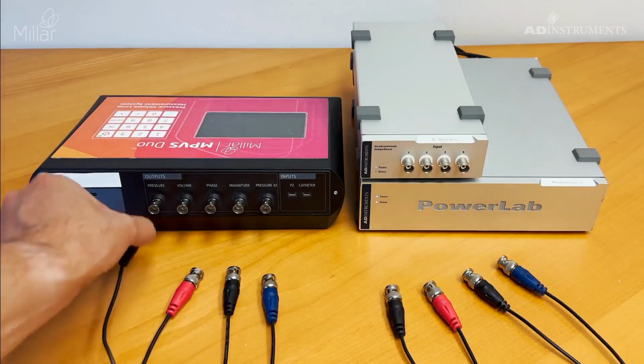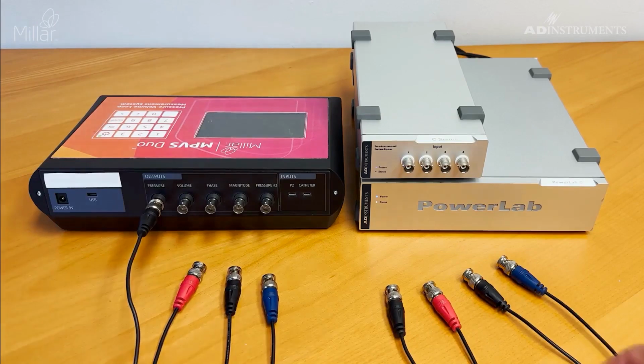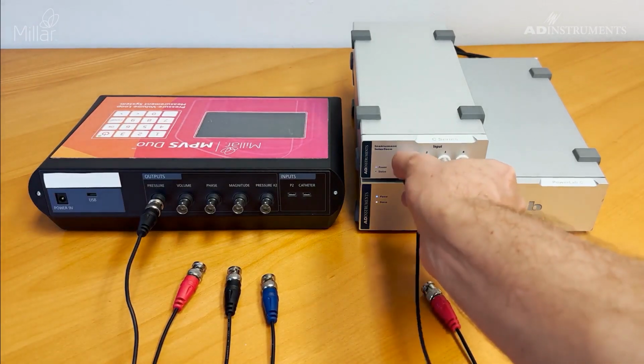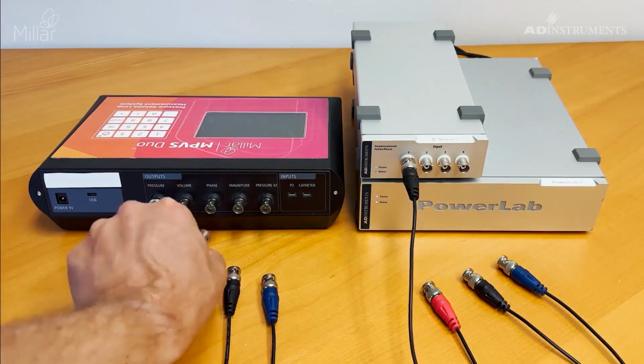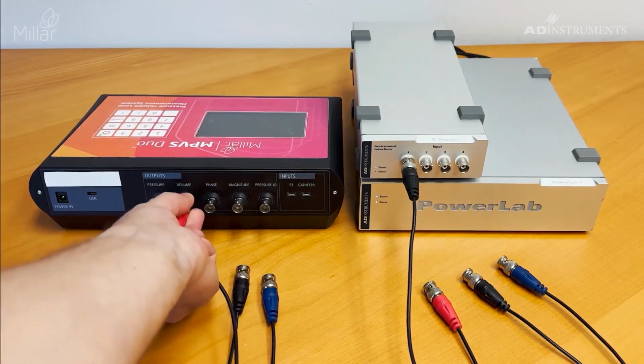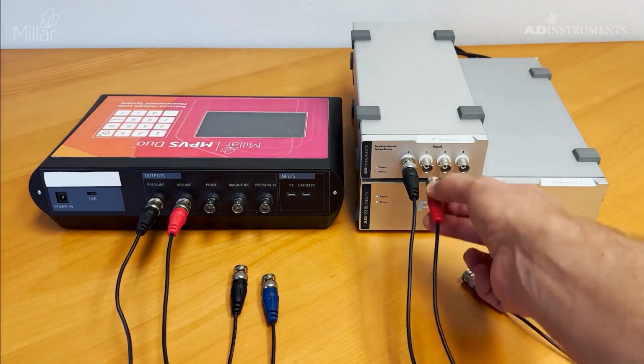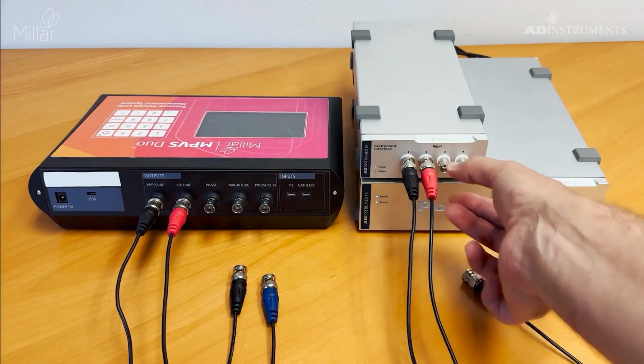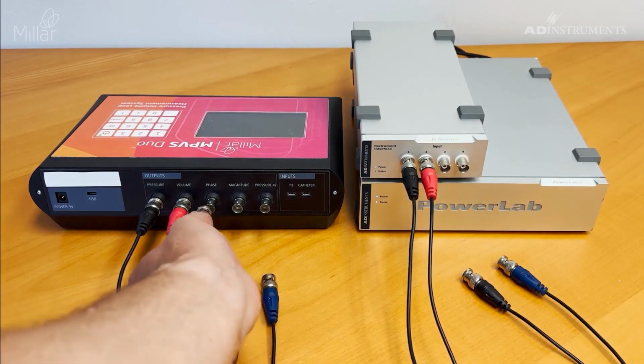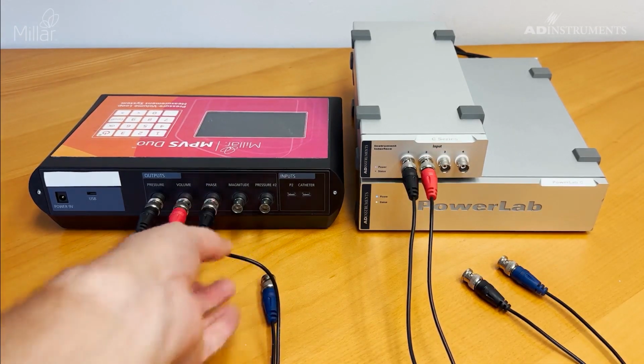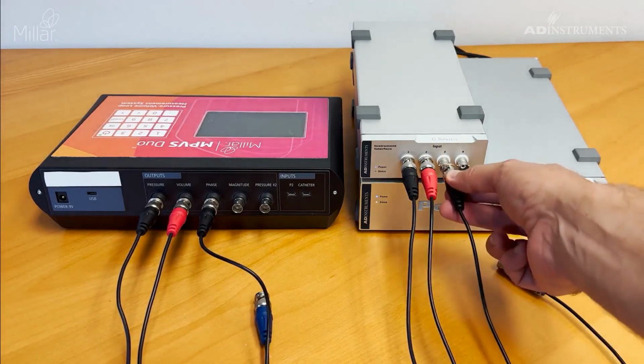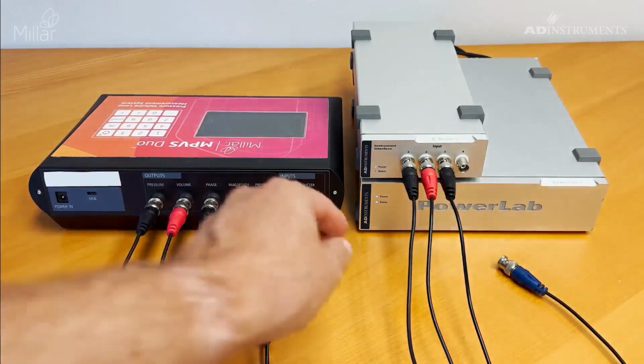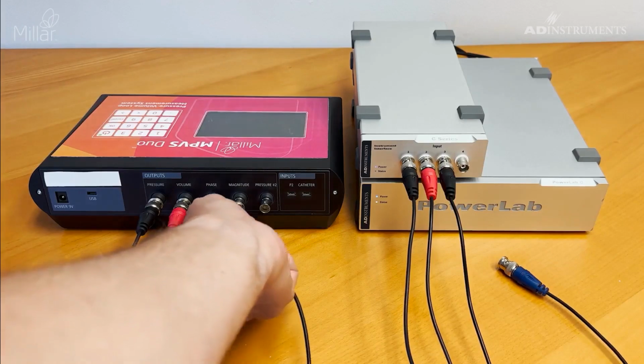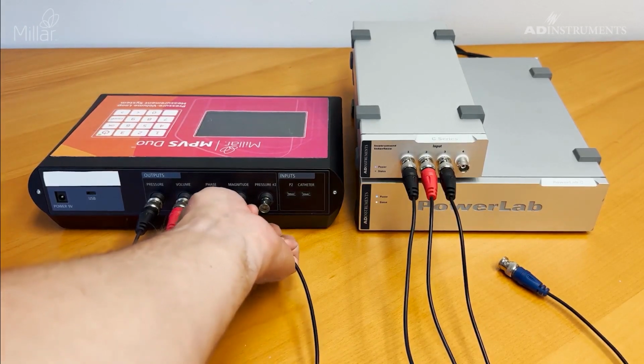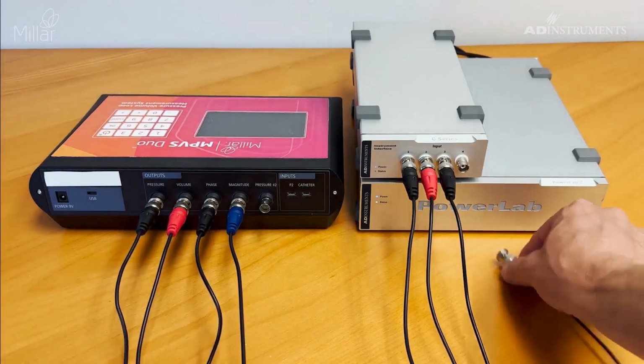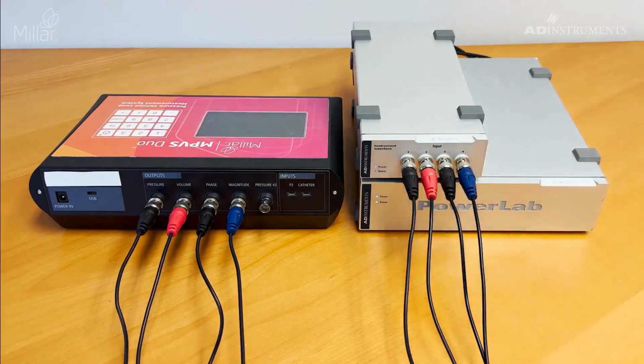For recording using admittance mode, I will connect pressure for ventricular pressure, volume for the calculated volume using the admittance technique, phase for showing the phase signal, which is used in catheter positioning, and lastly magnitude for displaying the measured admittance from the ventricle. This channel is synonymous with the total conductance measured from the heart.